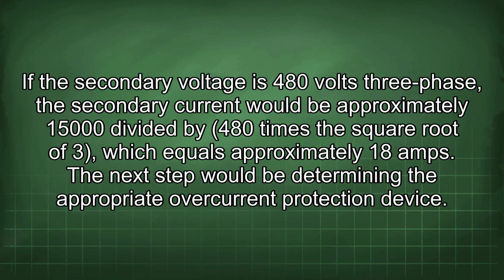If the secondary voltage is 480 volts 3-phase, the secondary current would be approximately 15,000 divided by 480 times the square root of 3, which equals approximately 18 amps. The next step would be determining the appropriate overcurrent protection device.